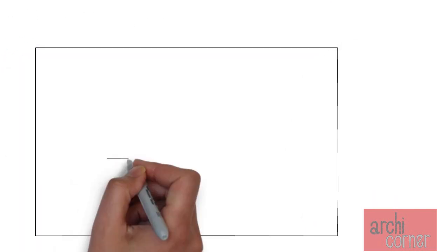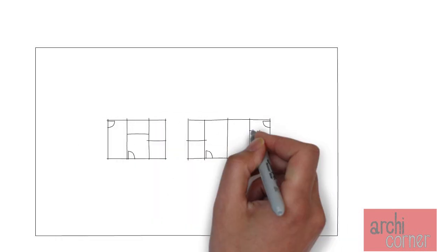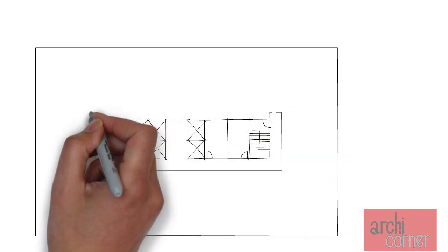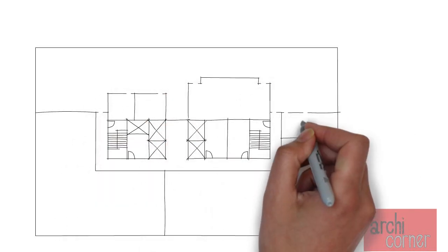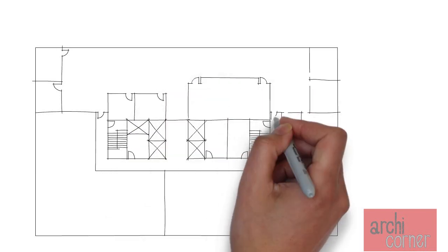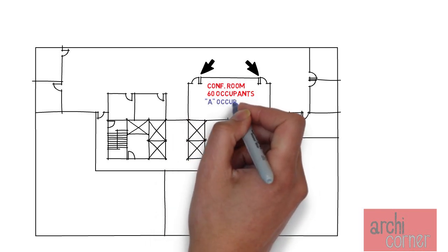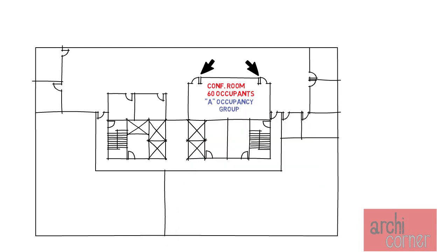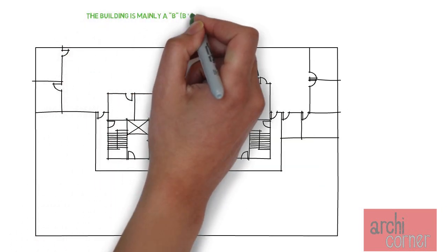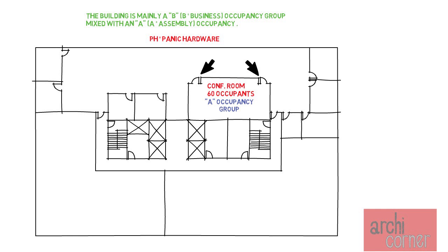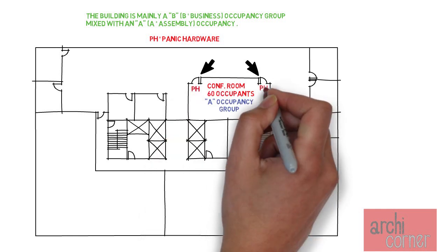Now let's see an example. This is a typical floor in a multi-story office building that requires the use of stairs to egress. It's not an A or E occupancy building overall, but there is a conference room with more than 50 occupants in this suite. This means the room requires two exits, and since it has over 50 occupants it is considered an A occupancy for egress purposes. Therefore, even though the suite is generally office use, this room is assembly use and is required to provide panic hardware on both doors.